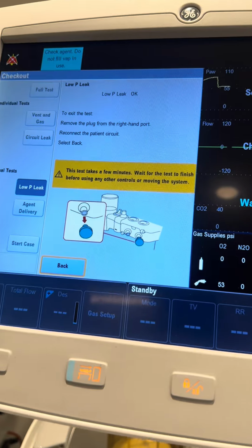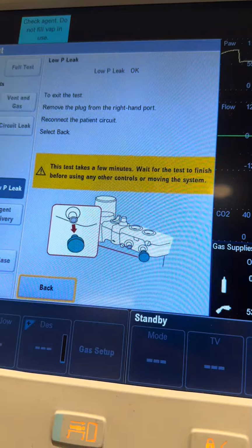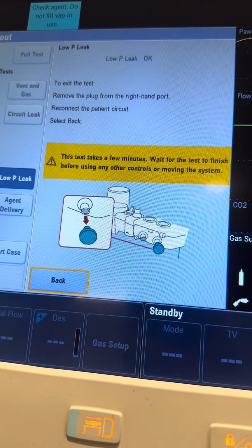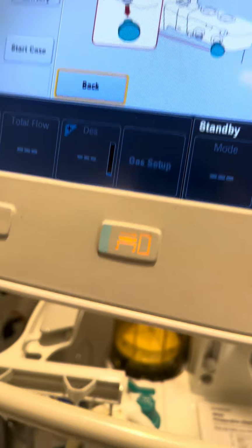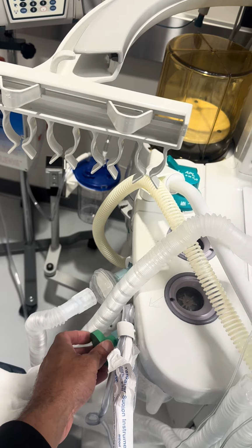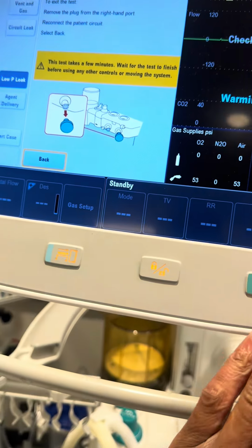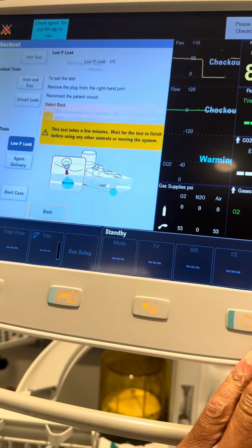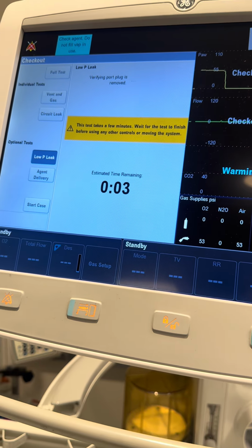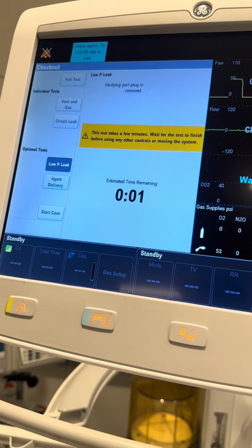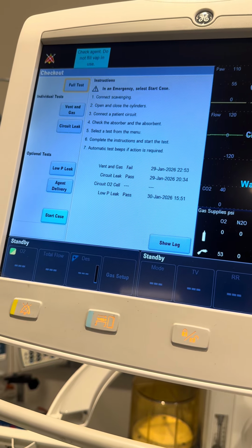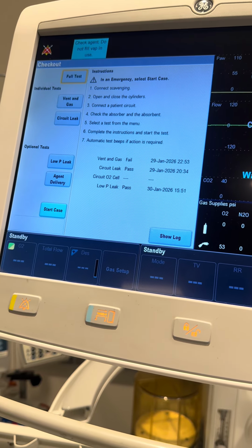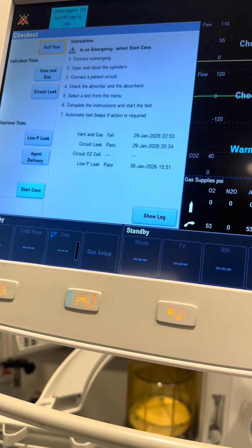You see right there, it says to exit the test, remove the plug from the right-hand port, reconnect the patient circuit, select back. So what we're gonna do is we're going to take this off, hit back with the switch, it's gonna verify the port is removed, the plug is removed, and you just successfully completed your Low P Leak.